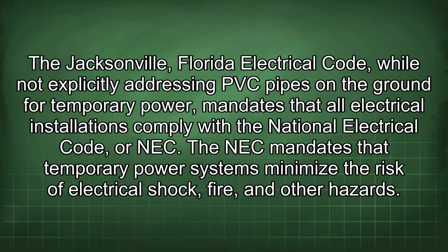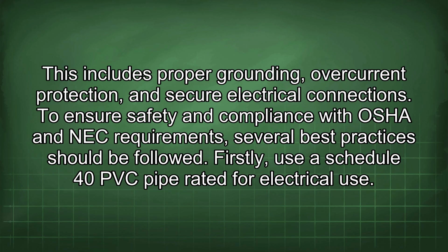The Jacksonville, Florida Electrical Code, while not explicitly addressing PVC pipes on the ground for temporary power, mandates that all electrical installations comply with the National Electrical Code, or NEC. The NEC mandates that temporary power systems minimize the risk of electrical shock, fire, and other hazards. This includes proper grounding, overcurrent protection, and secure electrical connections. To ensure safety and compliance with OSHA and NEC requirements, several best practices should be followed.